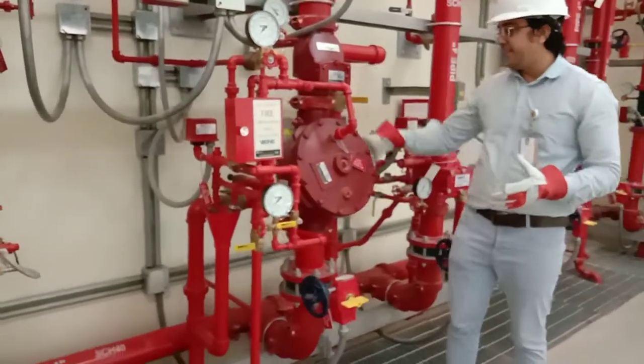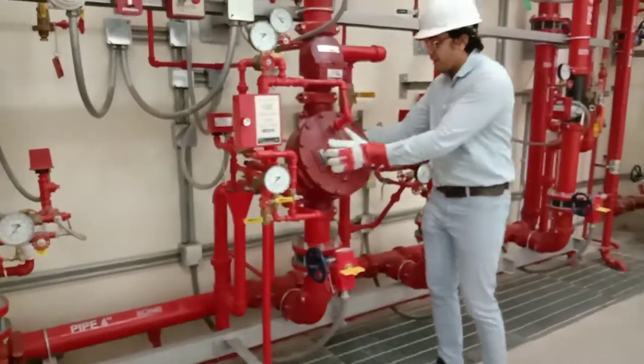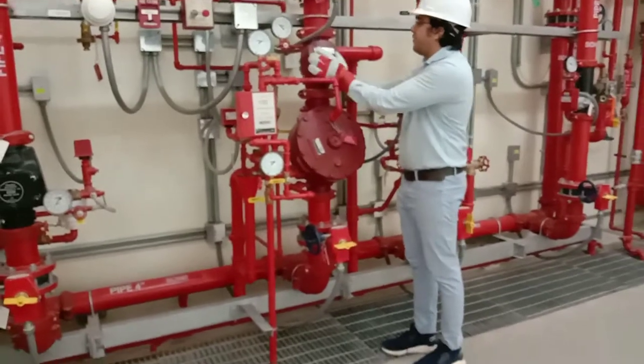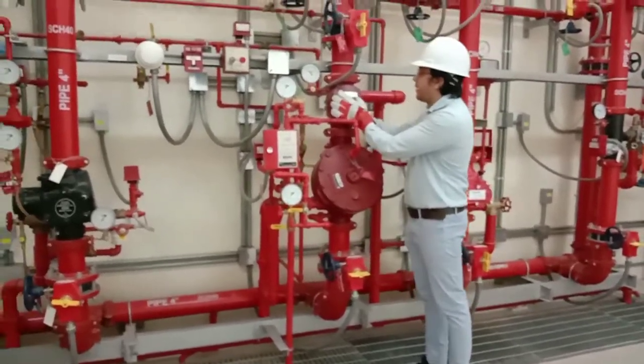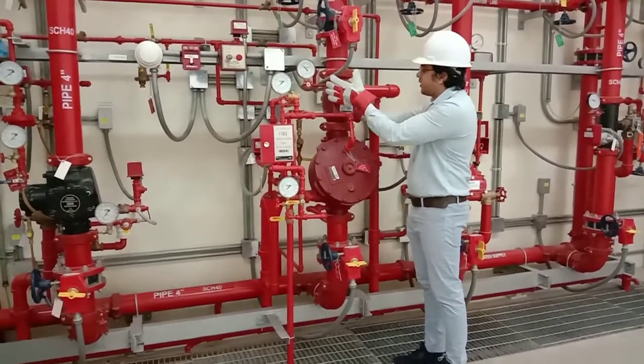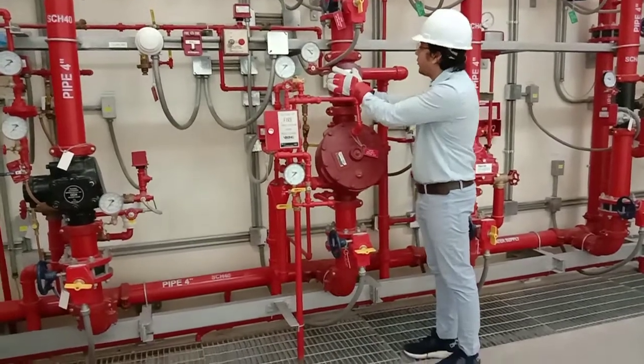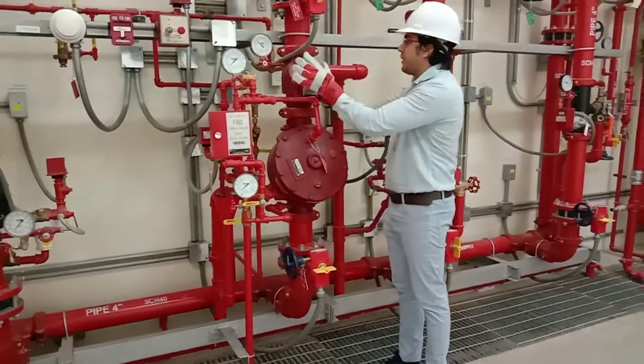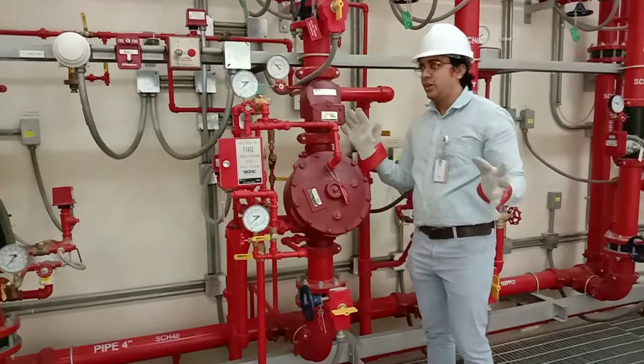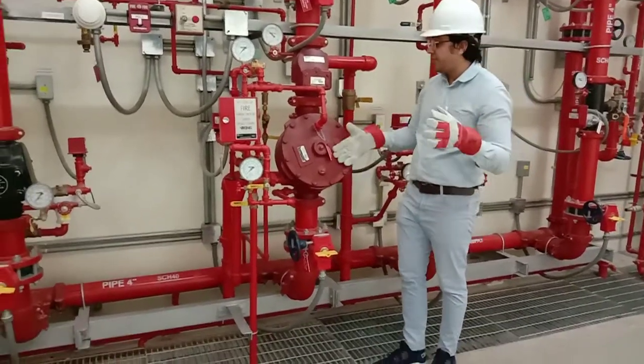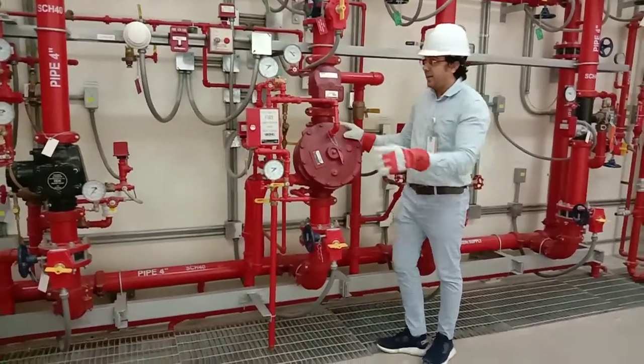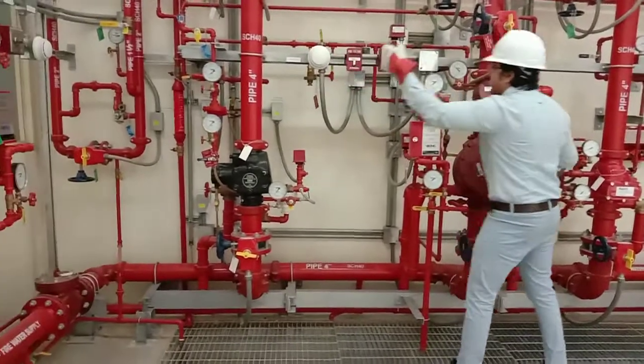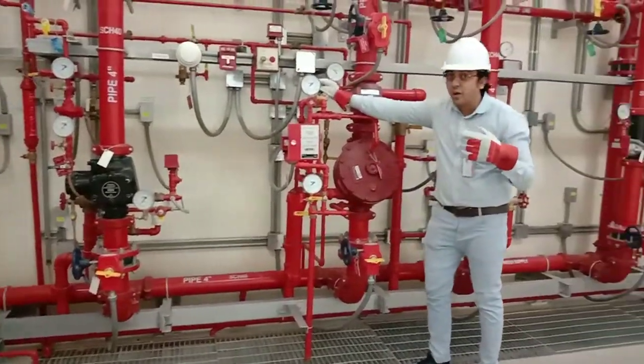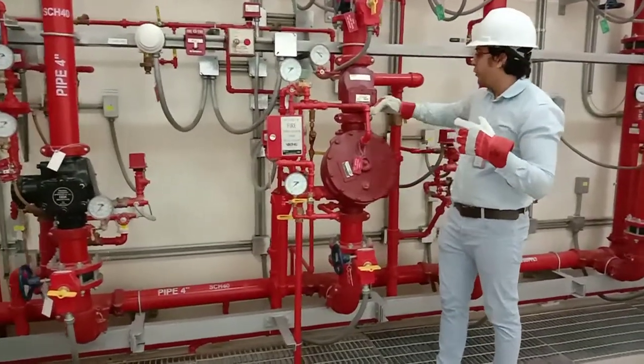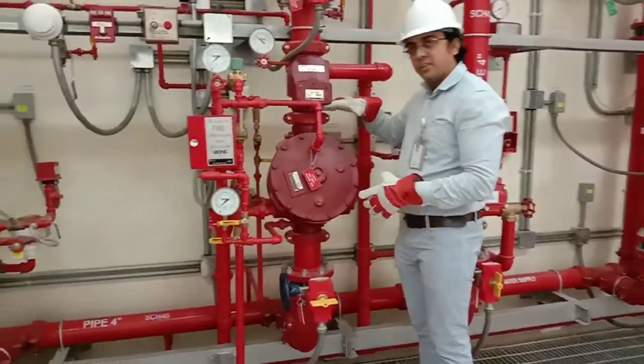Now, as I said, it's a deluge valve, right? This one is a deluge valve, and here we have a check valve, right? The AG riser check valve. So after the deluge valve, we need this kind of arrangement. As I said, in a double interlock pre-action system, if the system activates mistakenly by the detector, this detector gives a signal to the solenoid valve to open the valve, allowing water to go in. Water will go up to this location, right?